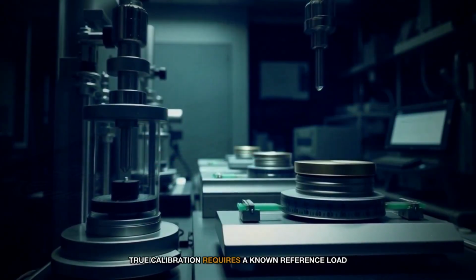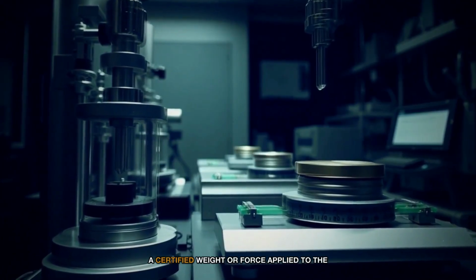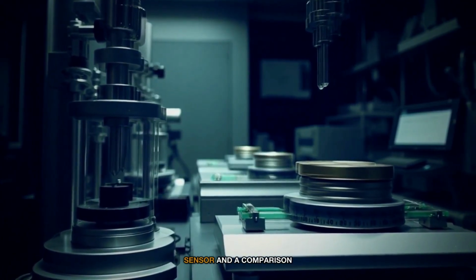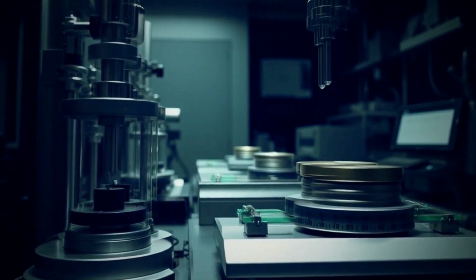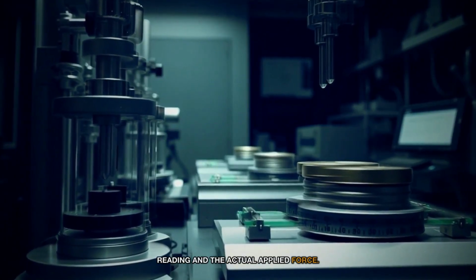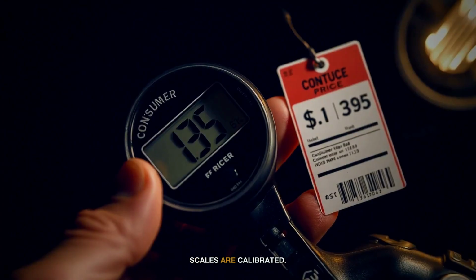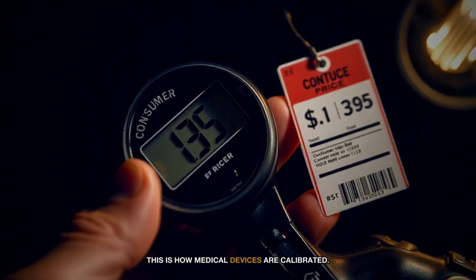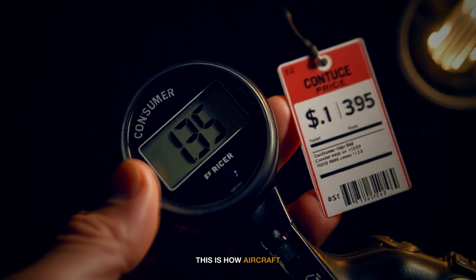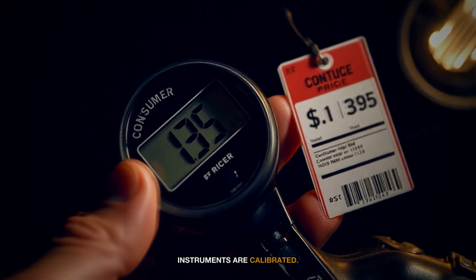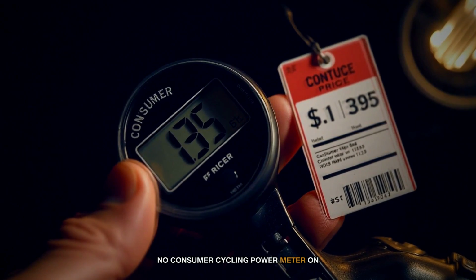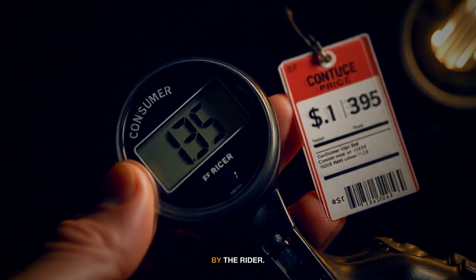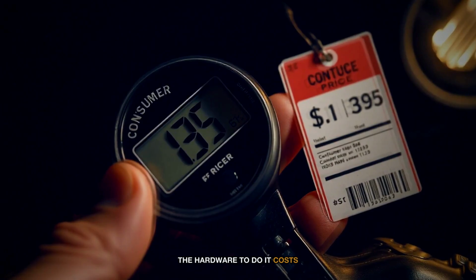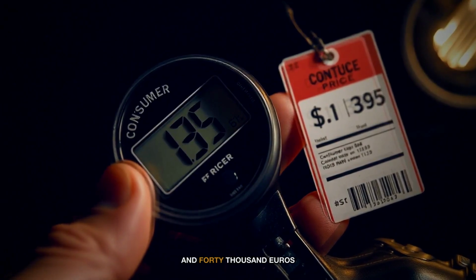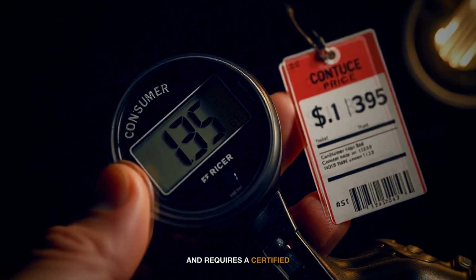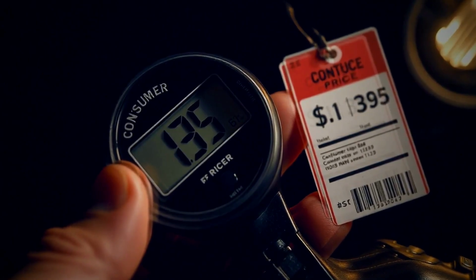True calibration requires a known reference load, a certified weight or force applied to the sensor, and a comparison between the device's reading and the actual applied force. This is how laboratory scales are calibrated. This is how medical devices are calibrated. This is how aircraft instruments are calibrated. No consumer cycling power meter on the market can be truly calibrated by the rider. The hardware to do it costs between 15,000 and 40,000 euros and requires a certified metrology laboratory.